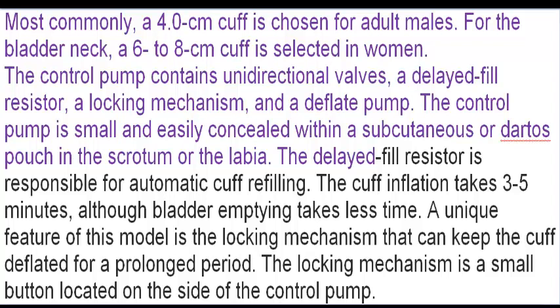The control pump contains unidirectional valves, a delayed fill resistor, a locking mechanism, and a deflate pump. The control pump is small and easily concealed within a subcutaneous or dartos pouch in the scrotum or the labia. The delayed fill resistor is responsible for automatic cuff refilling. The cuff inflation takes 3 to 5 minutes, although bladder emptying takes less time. A unique feature of this model is the locking mechanism that can keep the cuff deflated for a prolonged period. The locking mechanism is a small button located on the side of the control pump.